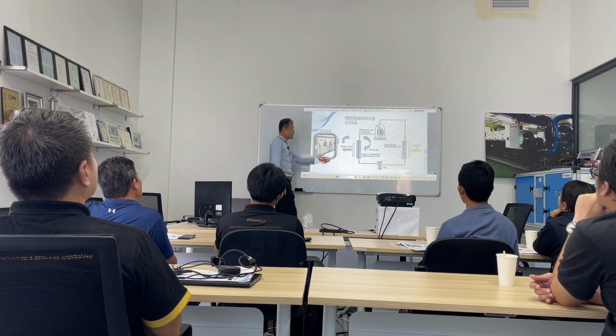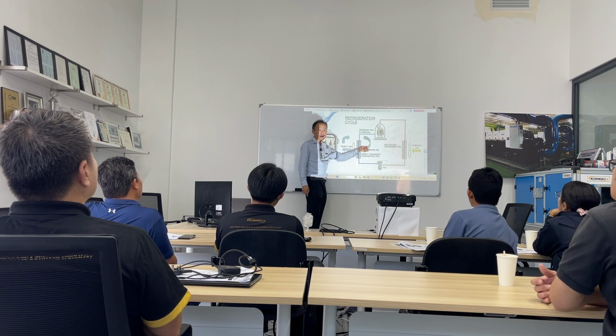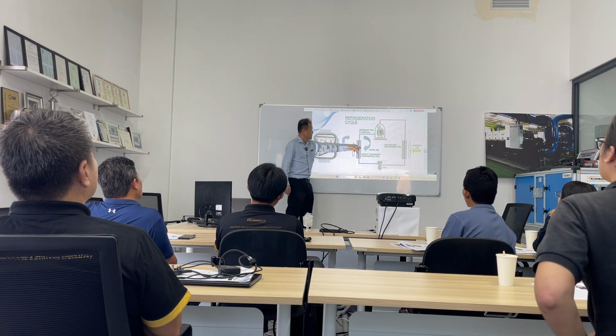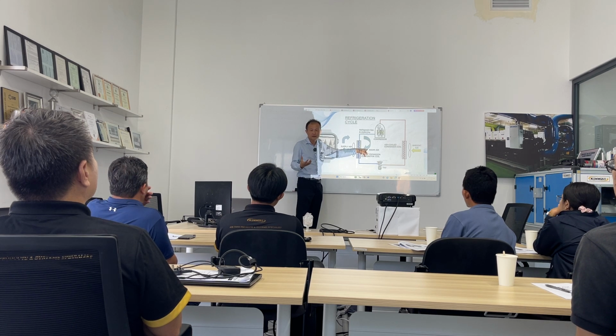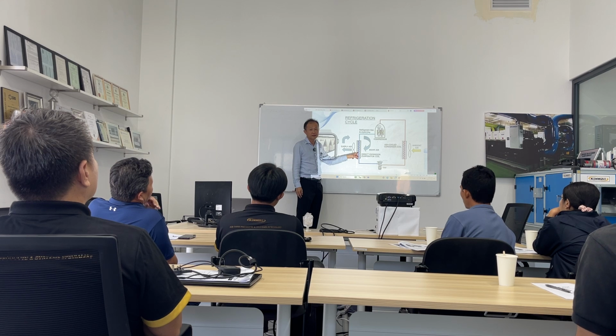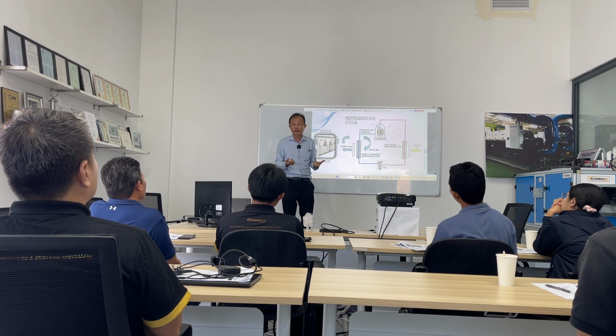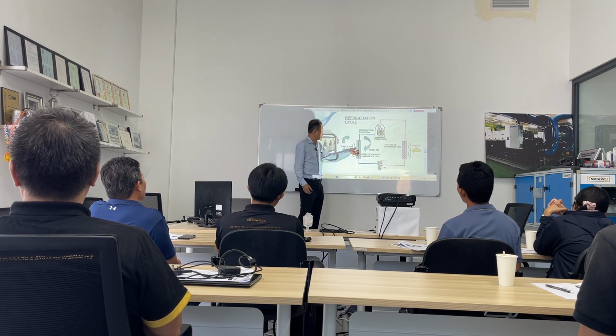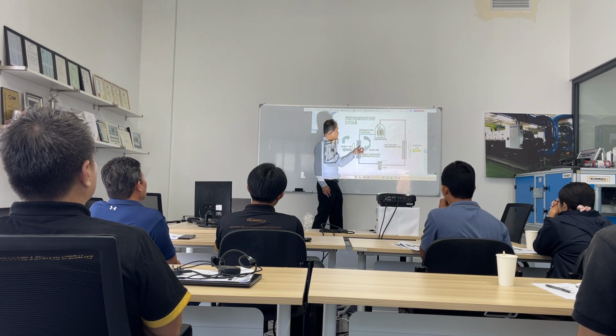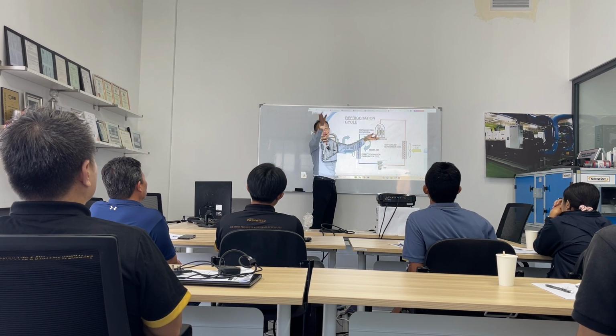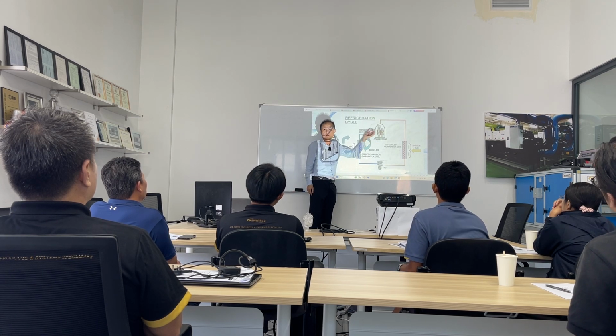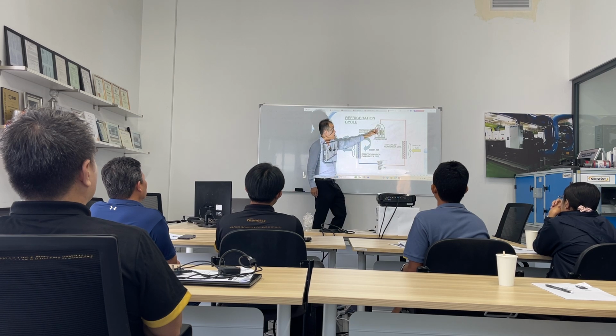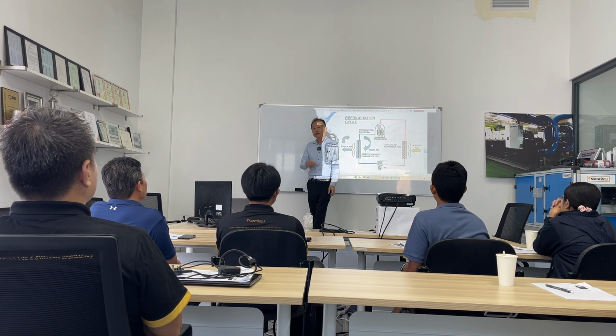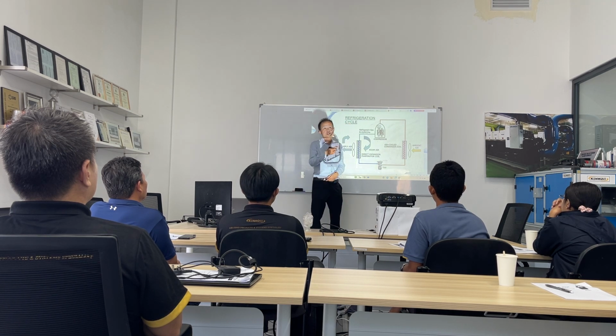When the air runs through the cooling coils, the room air, which is relatively warmer, transfers the heat to the refrigerant inside the evaporator, and the refrigerant directly expands. They call it a direct expansion system. Then the compressor sucks the refrigerant through the piping to the outdoor compressor, compresses it and pumps it at higher pressure into the condenser. When you raise the pressure of the refrigerant, its temperature becomes higher than the outdoor temperature, and it rejects the heat when the condenser fan blows air through the condenser coil.